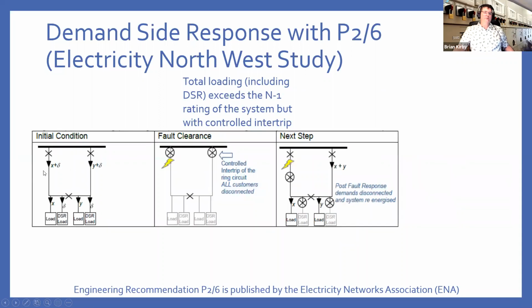You can also use an inter-tripping scheme so that if you detect a fault on the first feeder, you trip the second feeder as well. You shed the DSR load at that point. Then when you reconnect, you go back to a healthy state. So this is still in trial proposal stage at the minute. But as we move more and more towards renewable sources of energy, it may be that we need to move towards systems where you have incentives to people to say, okay, if you allow us to switch you off in these contingency systems, then we will reward you in some way.